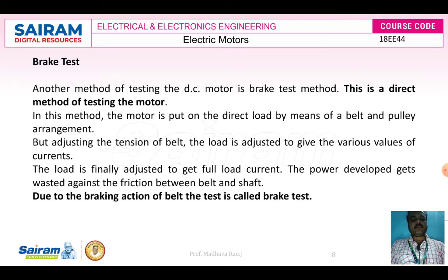Load being applied means we are applying brakes on the DC motor, so that we can test the DC motor at different loads. The load is finally adjusted up to the full load current. We cannot adjust the load beyond the full load current, because if you increase beyond it, the motor will heat up and get damaged.